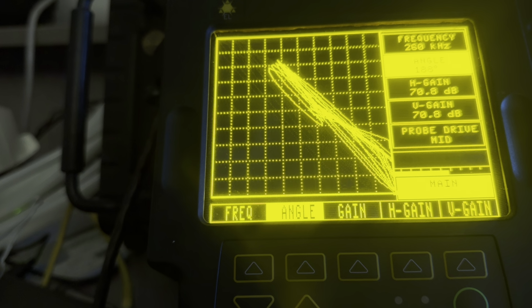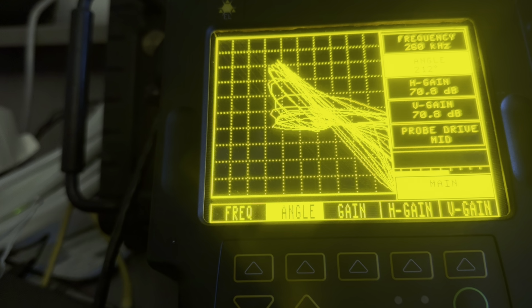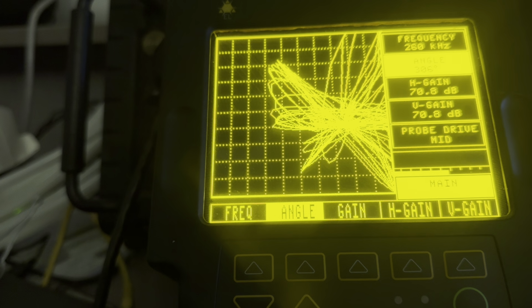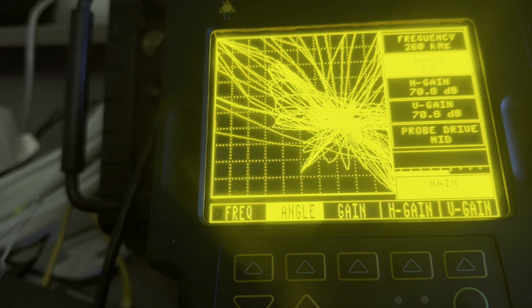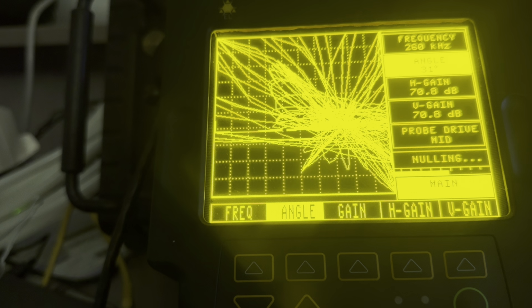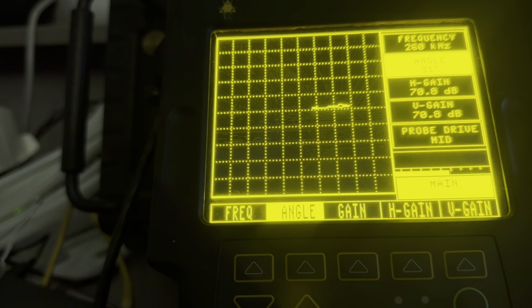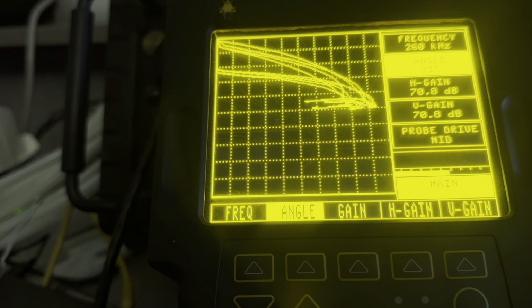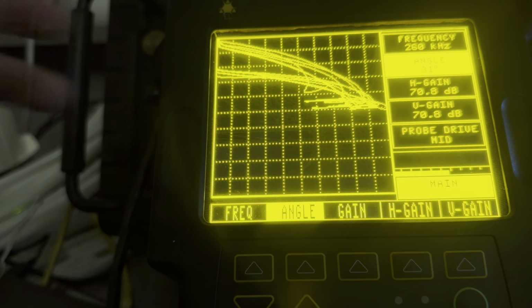Let's set some phase rotation on our liftoff. Okay, I know that my liftoff's upside down because when I pull a probe off, the impedance point goes to the right, but that's opposite of what we want. So here's where we do the old switcheroo. Put our liftoff back to horizontal. Now the loaded coil impedance point goes to the right. So we're going to hit null and then erase, and now we got some action. There's the largest EDM, medium, and then the smallest one. All right, so there's a Zetec 4-pin probe.